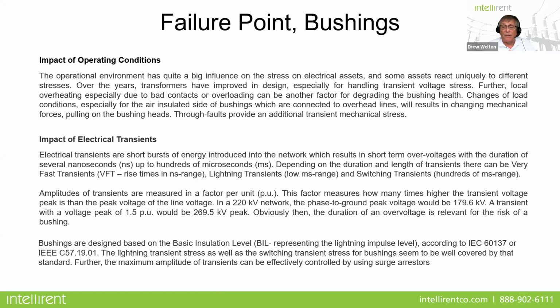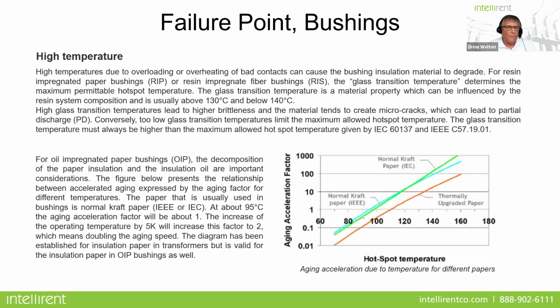And IEC 60137 or C57.19.01 has information regarding the correct BIL. And bushings need to be sized properly for the type and size of the transformer and the type of load. But lightning transient stress, as well as switching transient stress for bushings, seems to be well covered by that standard. So that's a good source of information. The maximum amplitude of transients can be effectively controlled, of course, by using proper surge arresters.